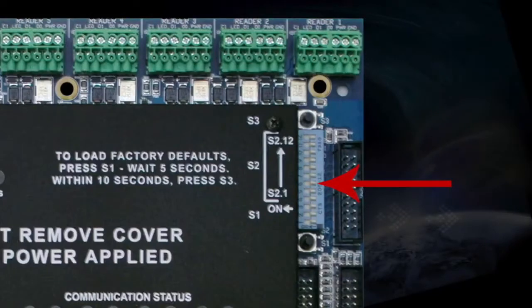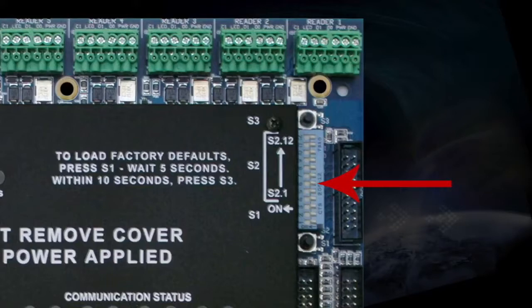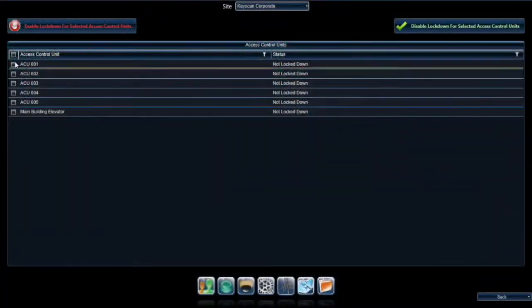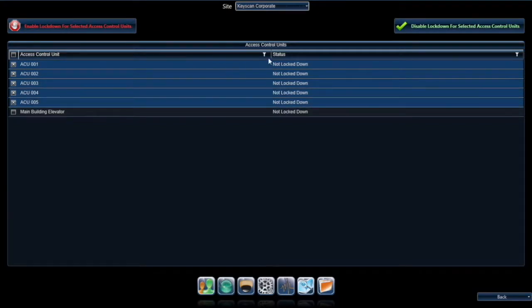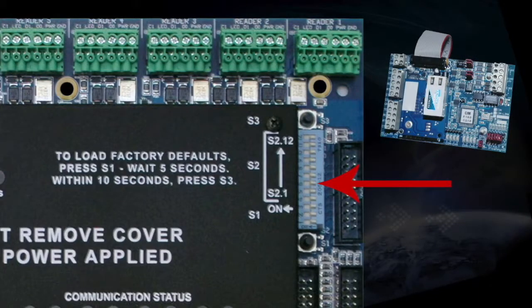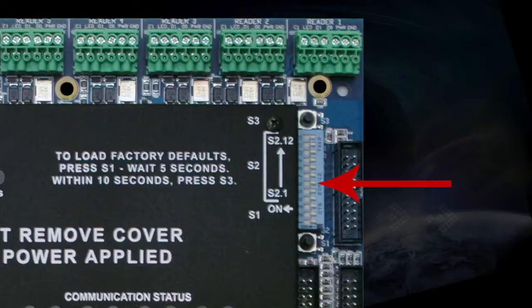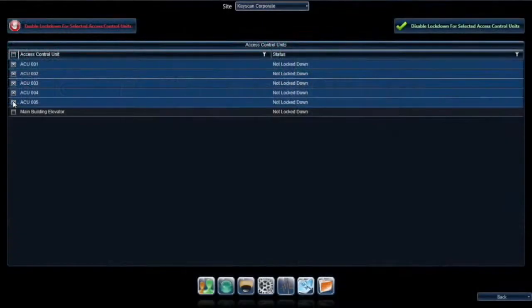Switch 6 is turned off by default. Turning this switch on will enable the lockdown functionality of the access control units, allowing you to trigger a lockdown event from an input on the unit. For CA 250s, input number 8 will become your designated lockdown trigger. On a CA 4500 or 8500, input 16 will be your designated input trigger. These inputs allow you to connect a device such as a panic button to initiate a lockdown event, and also give you the ability to lock down all enabled control units from the lockdown screen on the client software. For a global lockdown function, you will require a SIM module in each control panel.